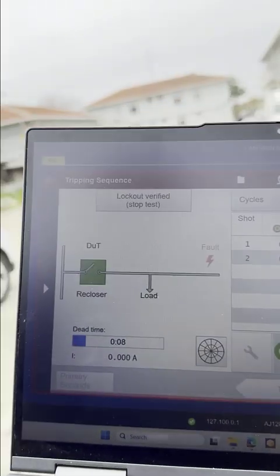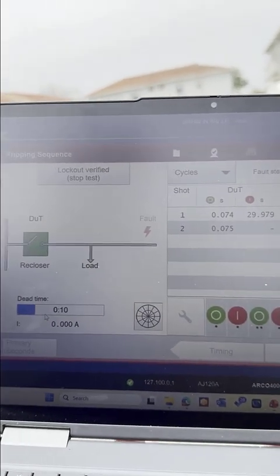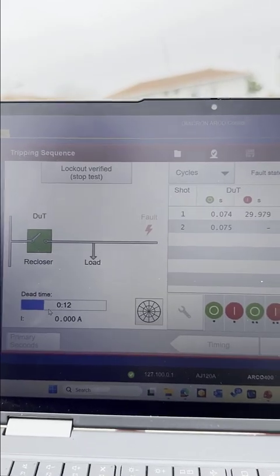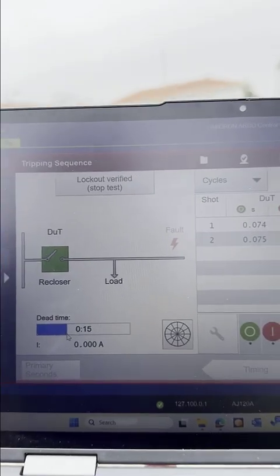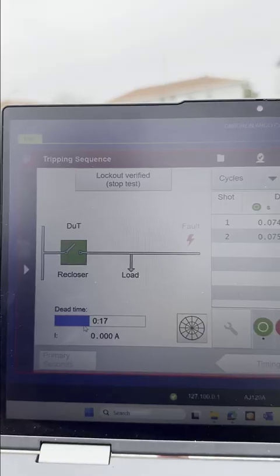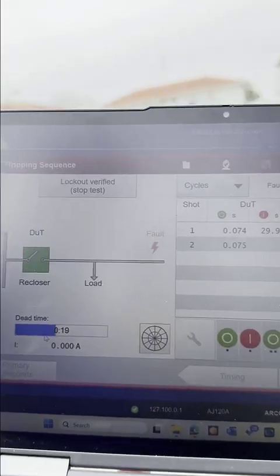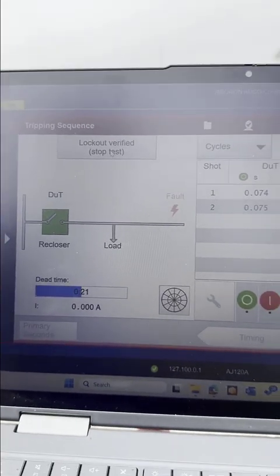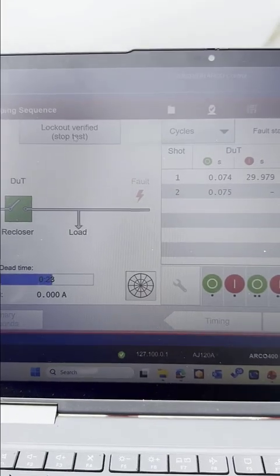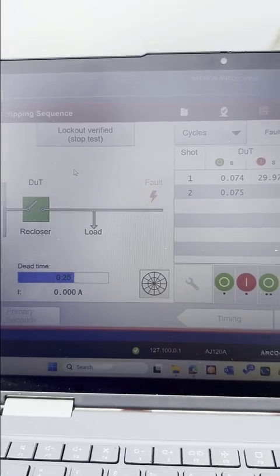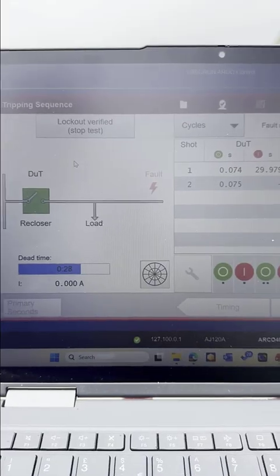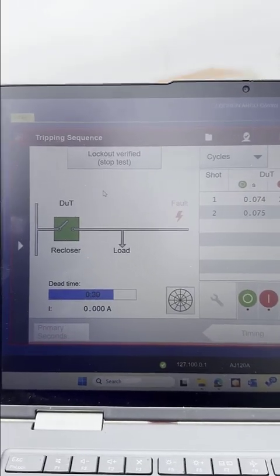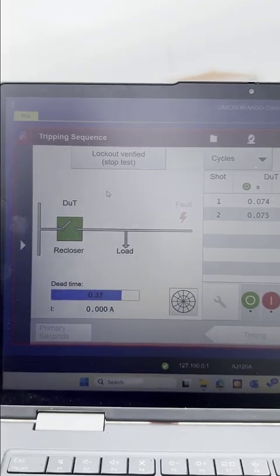And now we need to wait until the 40 seconds elapse just to make sure that the circuit breaker is locked out and there are no second reclose shots. Also, you can press here if the lockout is verified and you need to stop the test. Otherwise, you can wait until the 40 seconds elapse and the automatic assessment of the lockout status of the circuit breaker.